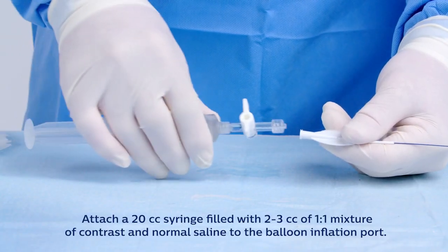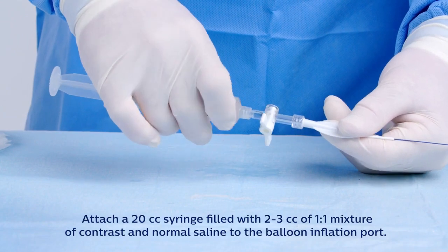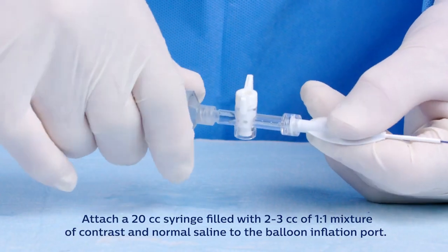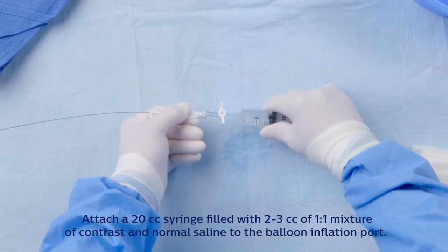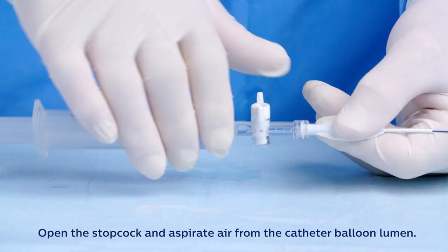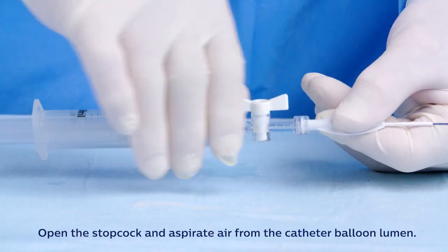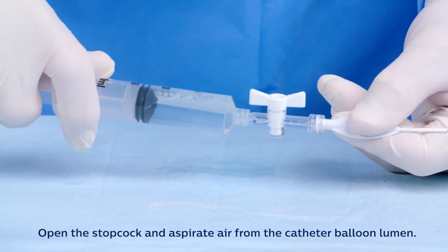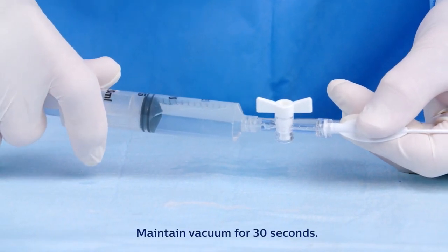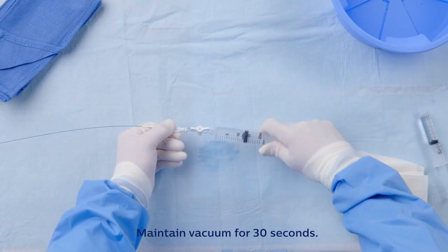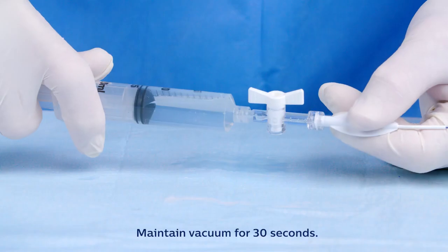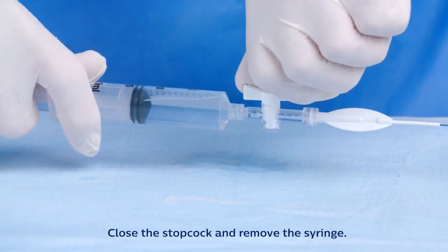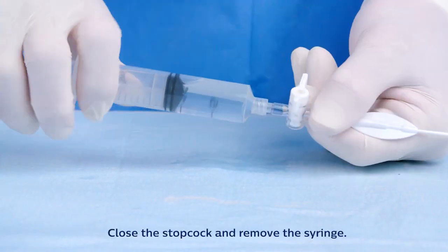Attach a 20 cc syringe filled with 2 to 3 cc's of 1-to-1 mixture of contrast and normal saline to the balloon inflation port. Open the stopcock and aspirate air from the catheter balloon lumen. Maintain vacuum for 30 seconds. Close the stopcock and remove the syringe.